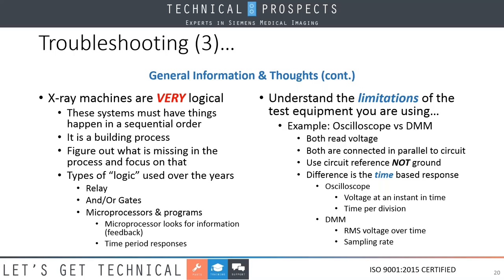All right. The difference between the two is an oscilloscope shows you a voltage at an instant in time. All right. And that's because we have a time per division knob on our oscilloscope. How do I know that? Because you can look at a signal, and by changing that, you can condense it or expand it out and measure that voltage at an instant in time. On a digital multimeter, though, it uses a sampling rate, which gives us the RMS voltage over time. Now, what you're typically going to find is the digital multimeter has somewhere between a 1 and 1.5 second response time before it can give you an accurate reading.